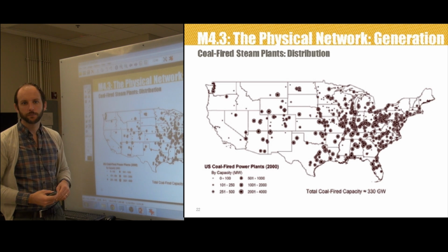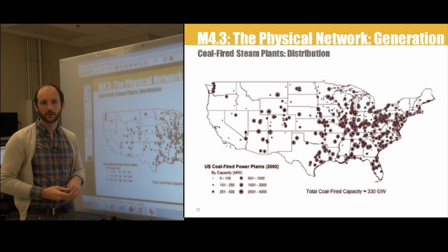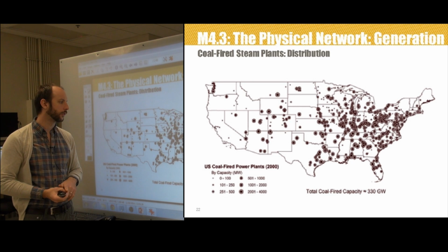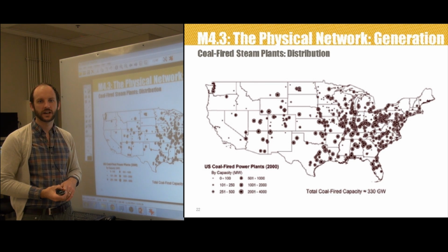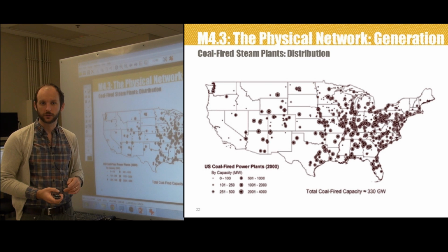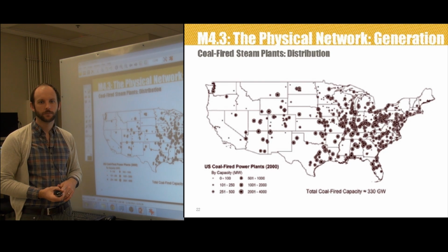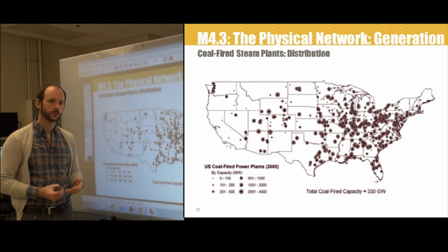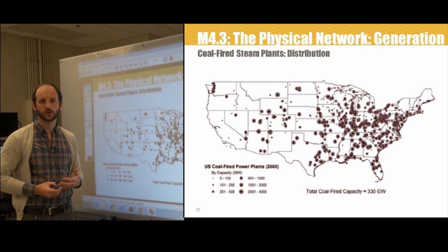Most of the coal-based generating units that operate according to the steam cycle in the U.S. are pretty old. 20 to 55 years old is kind of average, with a fleet average, I think, of about 35 in the U.S. Newer technologies are more efficient and tend to be larger. So if they're less than 35 years old, they tend to be about 550 megawatts.